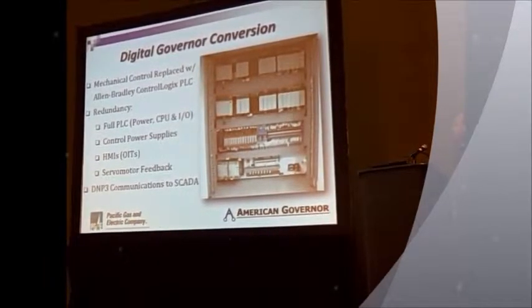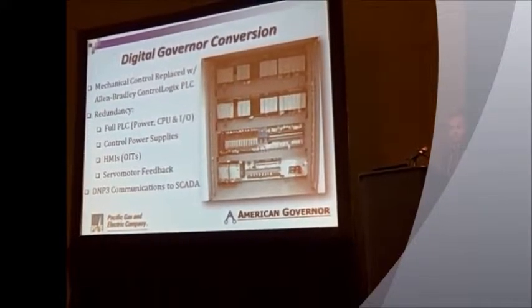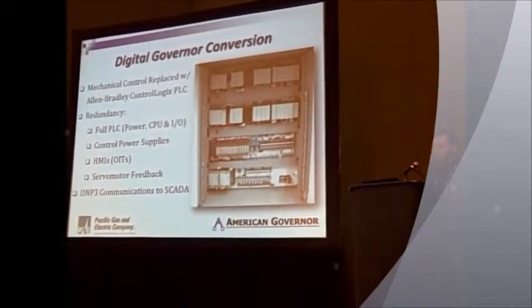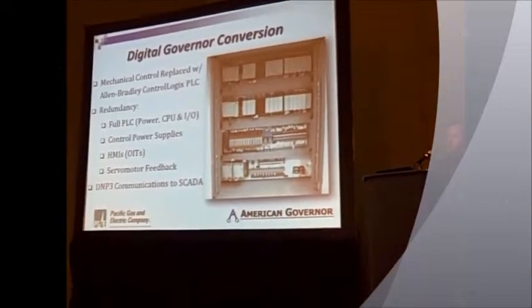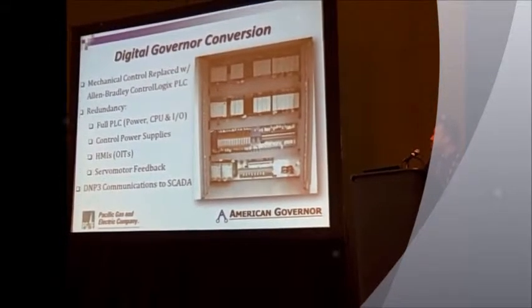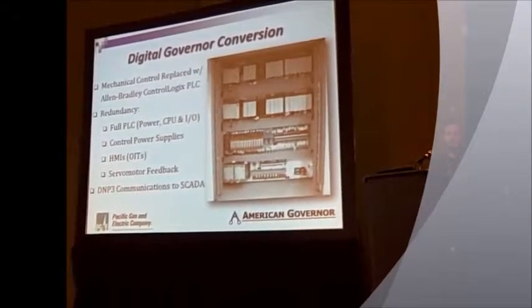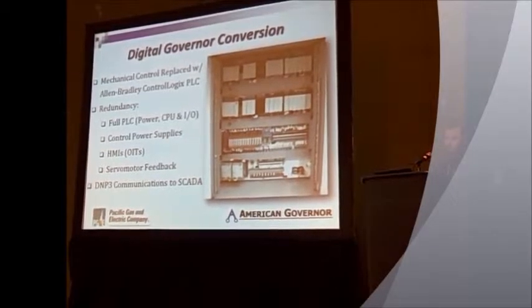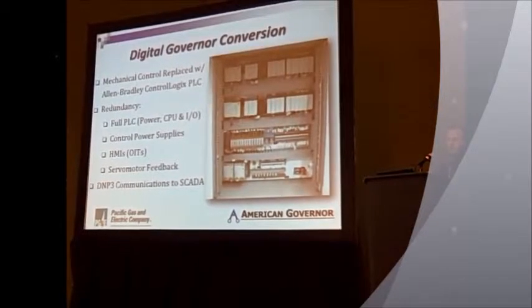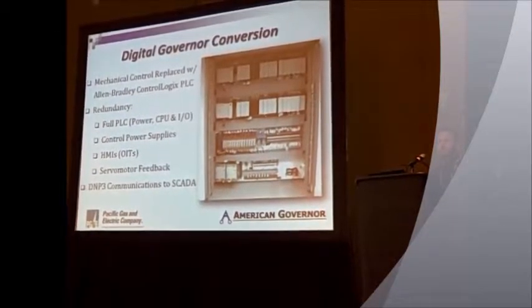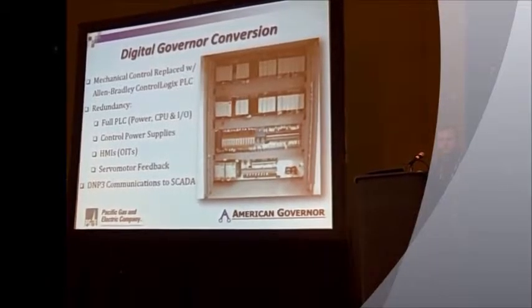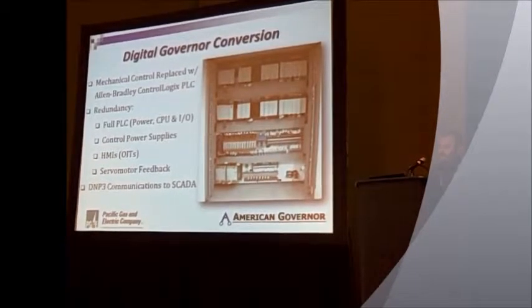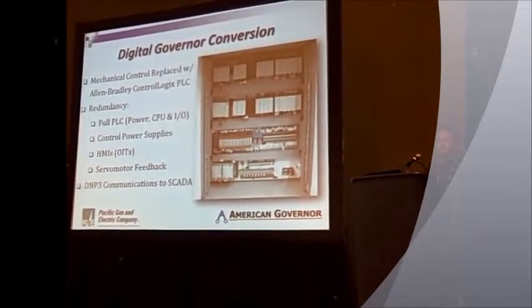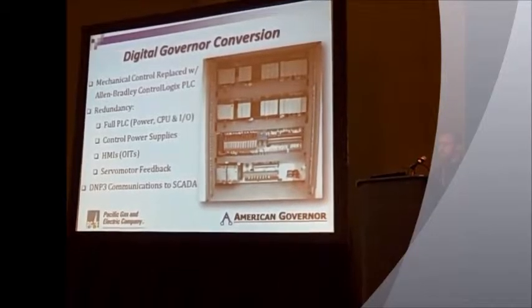So this is the inside of the control cabinet. We used Allen Bradley ControlLogix PLC, and because of the critical load following nature of Stanislaus, we went with a rather thorough redundancy configuration. We have full redundancy for PLCs, including power supplies, CPUs, and the I/O modules, using a redundancy configuration that we developed with PG&E and have used on several plants, including Kern Canyon and Helms Pump Storage. We have redundant power supplies, redundant HMIs, redundant servo motor feedback on the deflectors, but we do not have redundant servo motor feedback on the needles because the needles themselves are redundant. Also critical to the system is DNP communication directly to SCADA and more or less directly to the California ISO for set point communication.